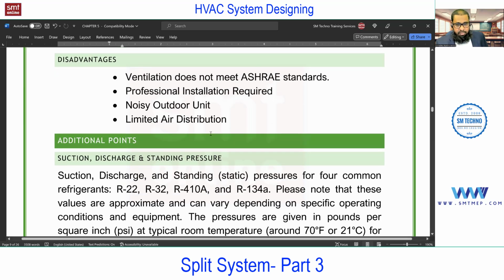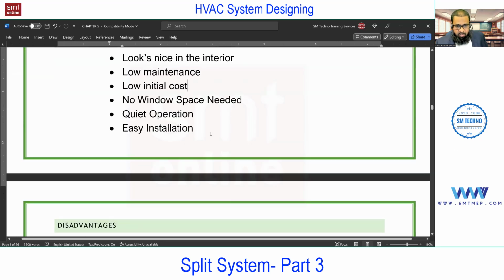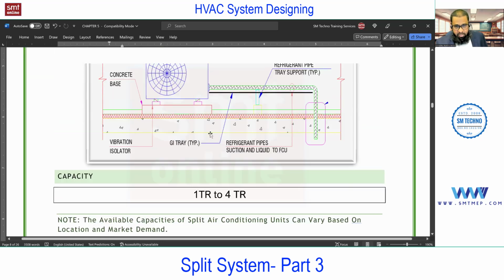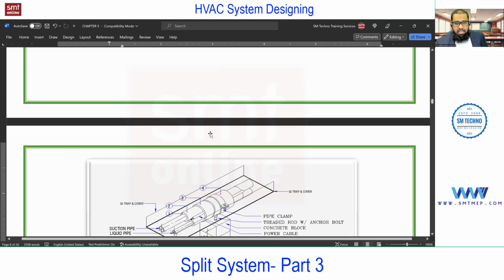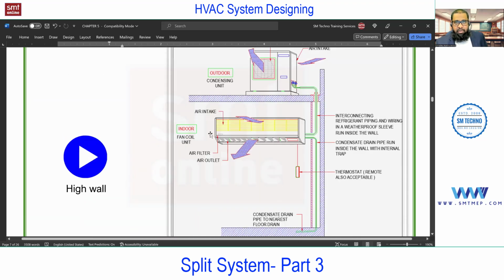And limited air distribution. This is also one disadvantage. Not only in high wall, even in window units you will find poor air distribution, because the air is supplied from one outlet. If you talk about the definition of air conditioning, motion and distribution is also one parameter. But in this, we are supplying the air from one outlet, from one side of the wall, so the distribution of air is poor. This can be overcome by using a ceiling fan, which is what we do in actual practice in India or even in the Gulf. With the split AC, we use a ceiling fan. The ceiling fan helps to circulate the air, and the high wall FCU provides the cool air.